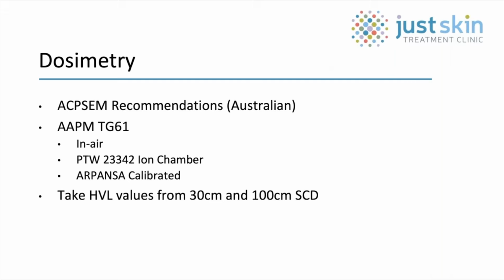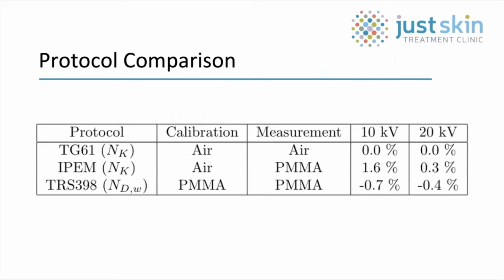As per these recommendations, I use the AAPM Task Group 61 protocol. I predominantly used a PTW 23342 thin window ionisation chamber, which was calibrated in Melbourne, Australia by the Australian Radiation Protection and Nuclear Safety Agency. They were able to calibrate my chamber down to 10 kilovolts. I repeated the absolute dosimetry using the IPEM and TRS-398 protocols. As you can see, I got very similar results using each protocol. This was a great sanity check, and getting my head around the other protocols was a great learning experience.